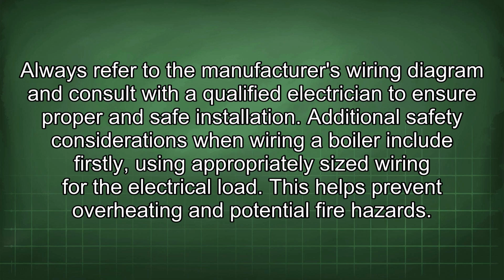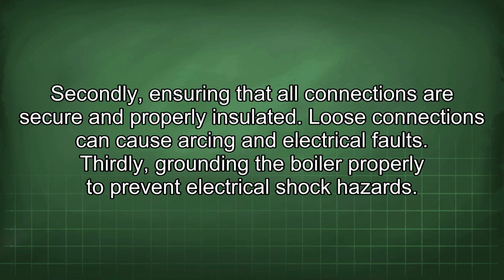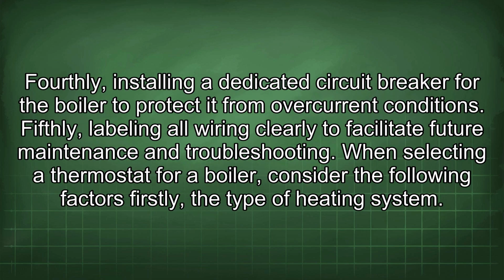Additional safety considerations when wiring a boiler include, firstly, using appropriately sized wiring for the electrical load. This helps prevent overheating and potential fire hazards. Secondly, ensuring that all connections are secure and properly insulated. Loose connections can cause arcing and electrical faults. Thirdly, grounding the boiler properly to prevent electrical shock hazards. Fourthly, installing a dedicated circuit breaker for the boiler to protect it from overcurrent conditions. Fifthly, labeling all wiring clearly to facilitate future maintenance and troubleshooting.